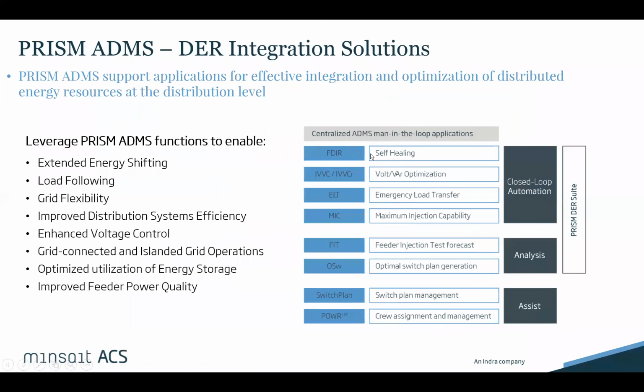And just as an example, we have functions that we refer to as emergency load transfer, injection capability, and feeder injection forecast that are all used to help maximize the penetration, or maximize the injection, of PV on the network without having to curtail. So we use integrated volt VAR control along with load transfer and switching to help mitigate any voltage issues, temporarily transfer load to manage voltage, and ensure that any PV on the network can be used without curtailment. Simply one example of the solutions that we have available.